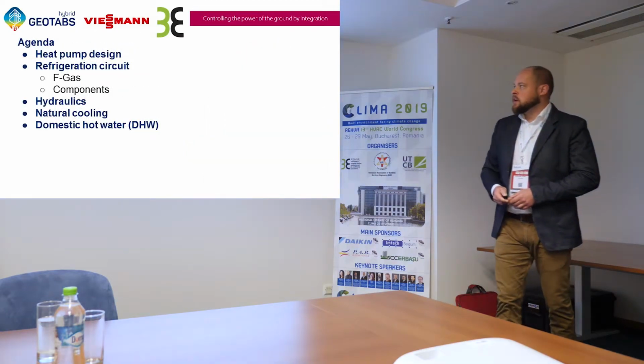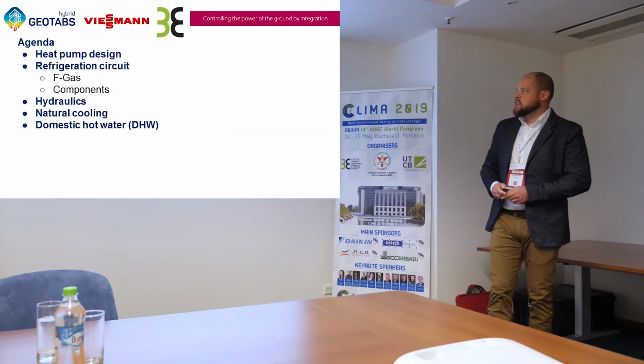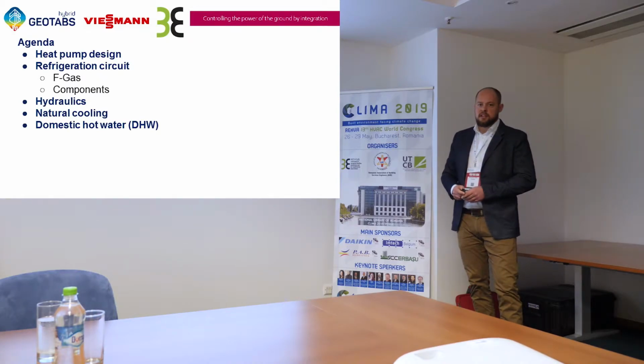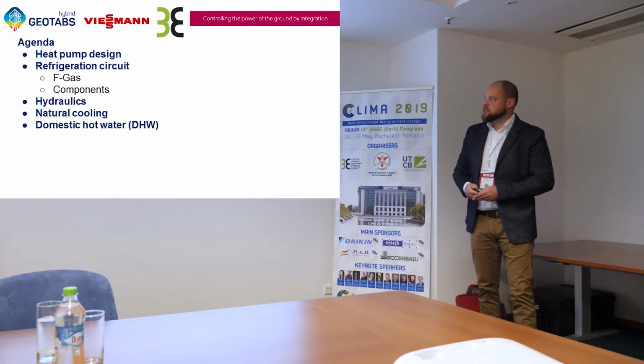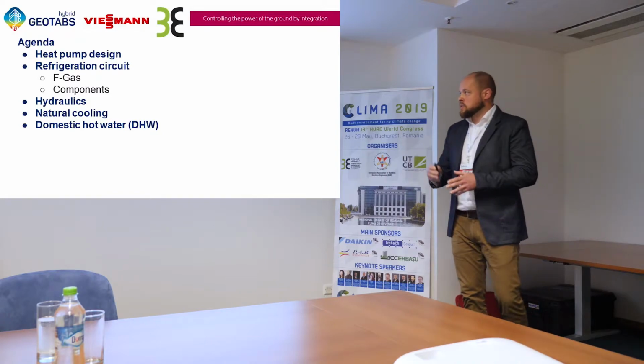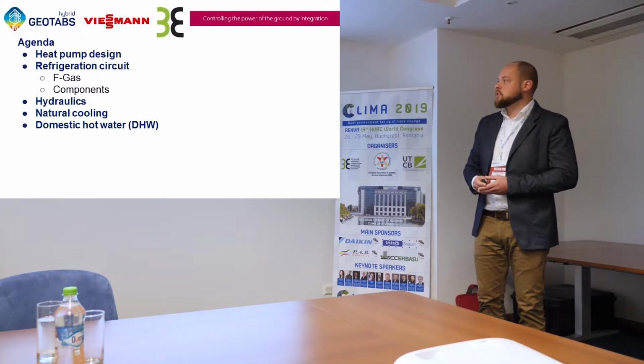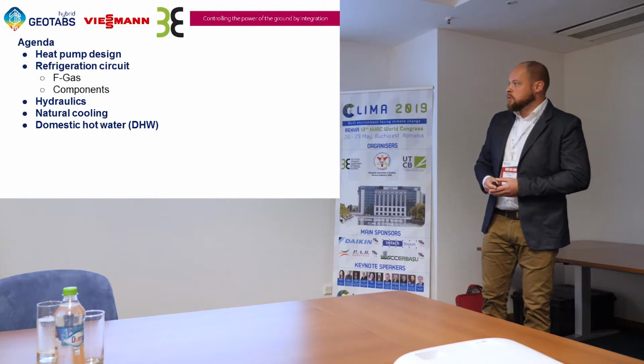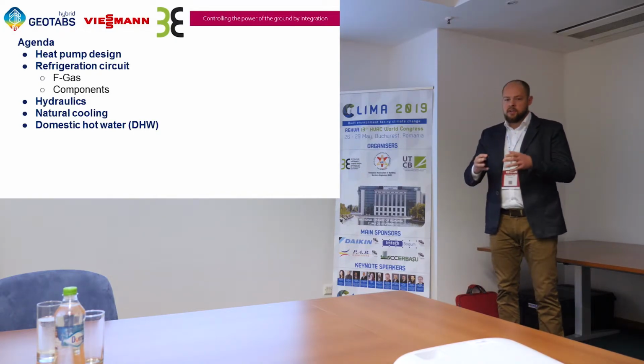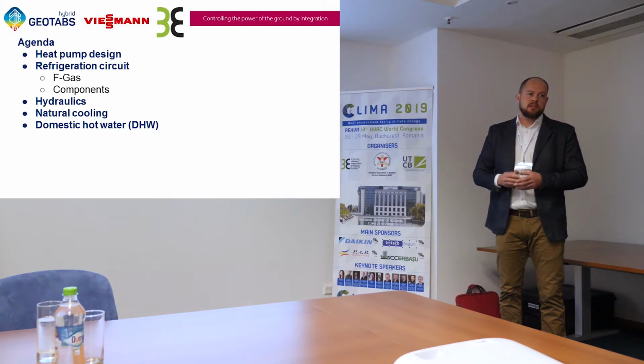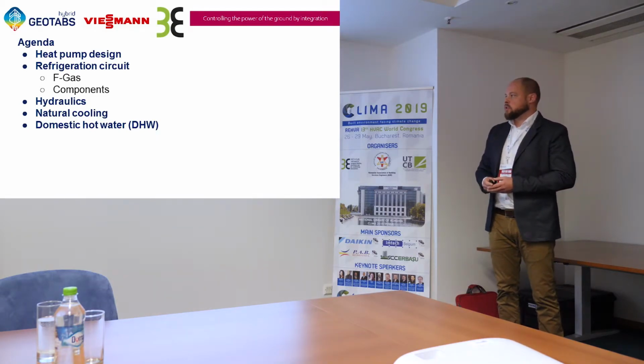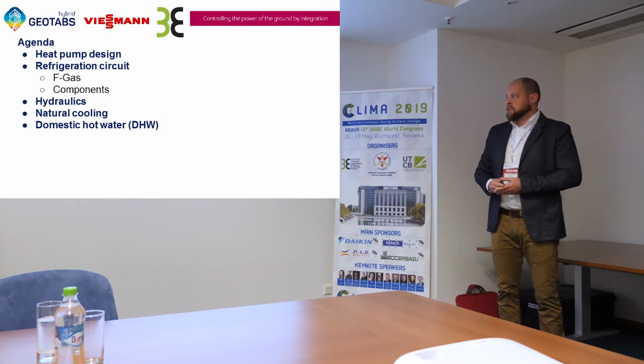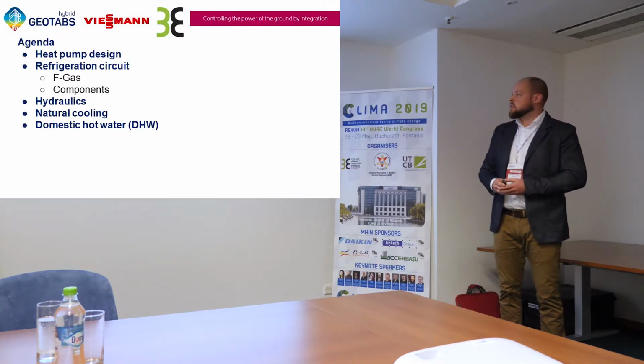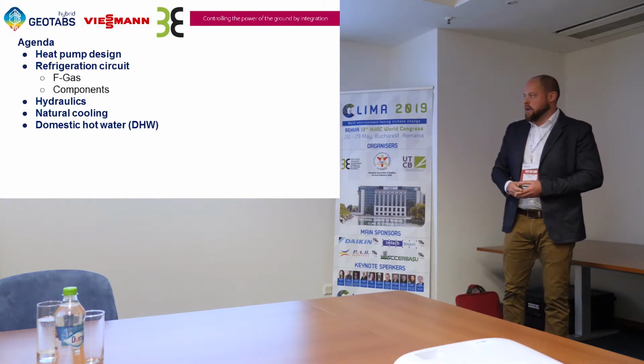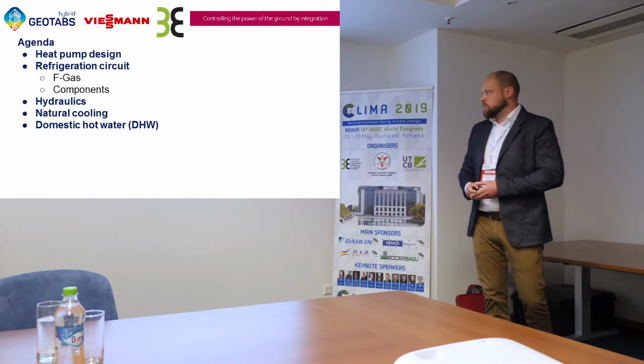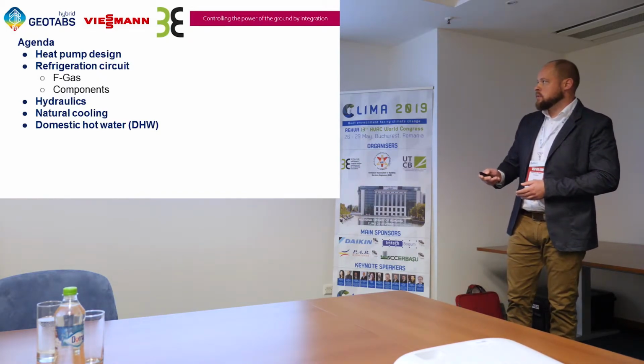Okay. So today I'm going to talk about the heat pump design, a bit about the refrigeration circuit inside the heat pump, the F-gas regulation that is upcoming, and the influence of the F-gas regulation on the different components. Also I'm going to talk about the hydraulics, how a heat pump is integrated in the building, which are different solutions and working conditions. Another aspect is the natural cooling, we saw it in the presentation of Hectro. And then we have the domestic hot water, also a very important part of the building.